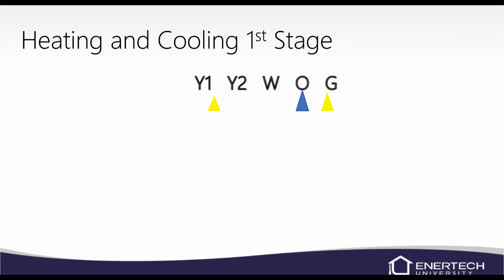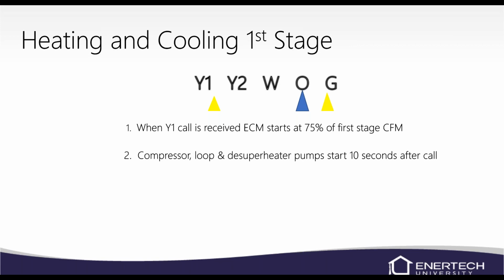So we're in heating and cooling first stage. If you're in cooling, you're going to have an O. And if you're in heating, you're going to have a Y1, a G call, and that'll be your first stage of your compressor. Once it realizes that you have that Y1 call, the ECM is going to start at 75% of first stage CFM levels. Then about 1 to 10 seconds after that call has come in through the lockout board and your ASC, or your anti-short cycle timer, has expired, the compressor, your loop, and your de-superheater pumps are going to start. After that, the ECM will adjust to 100% of first stage CFM levels about 30 seconds after the call.